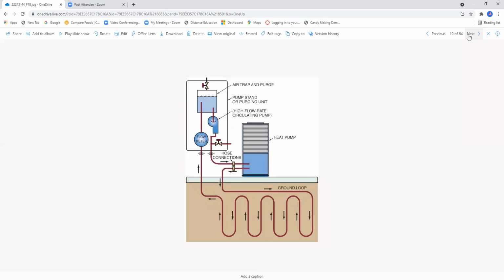Okay, here we have the heat pump, one form of it. And notice that you have a heat pump, you have your hose connections, you have the ground loop down below, and it's very environmentally friendly as far as the makeup of this thing. This particular illustration is located on page 1335 of your textbook under 44.18. Schematic showing the purging unit hooked up to the heat pump for power flushing air and debris from the ground loop. So when you commission these systems, you have to purge them. You have to make sure they're free of air prior to putting these things in service.